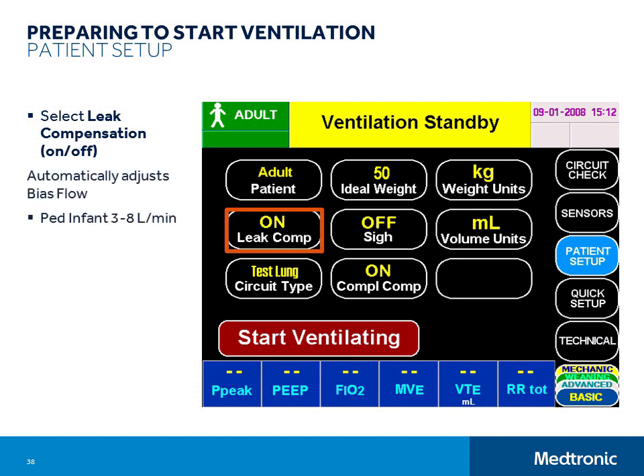Leak compensation can enhance patient trigger reliability because it can significantly reduce the chances of auto-triggering in spite of varying airway and circuit system leaks. The e360 ventilator automatically coordinates the flow-trigger relationship to leak compensation flow, so there is no need to readjust the flow trigger when a leak changes. This makes this system virtually hands-free in spite of a changing leak.